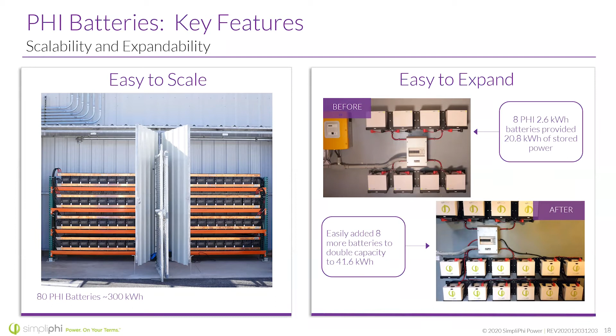Our batteries are self-contained and stable. They do not off-gas, they do not need ventilation, and they don't really need a lot of work over time. You're not watering them or checking specific gravity or anything like that. And they have an extremely low self-discharge rate, about 1% per month. This means they can stand idle very well. So if the SOC is really high and the power goes out, your power is there because it's been staying idle. It's not like a lead acid battery, like a car battery, where it just sits there and loses a lot of stored energy over time. These don't have that problem, with a self-discharge rate of less than 1% per month.